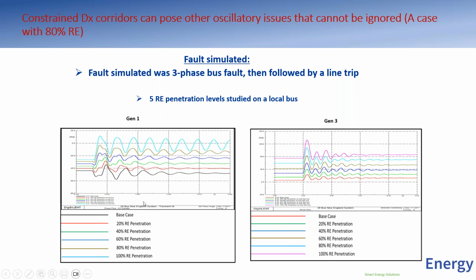Then you'll find you start experiencing instability as far as transient stability is concerned. Sometimes things are not so nice. You may find corridors at distribution level, where you're integrating this renewable generation, are already constrained. Once already constrained, you're likely to have transient stability problems instead of improving them. The remaining synchronous machines tend to become unstable, you don't relieve them in that case, because now by adding the generation you're no longer solving the problem.